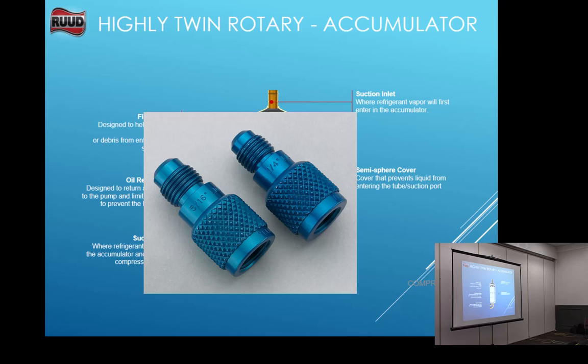Mm-hmm. It does. But once you do it for 2 or 3 weeks, you will get used to it. Because none of the refrigerants we use anymore are supposed to go in the suction line as a liquid. Okay? I'll pass this around. Y'all can look at it. But just keep that in mind. Okay? It's going to save you from killing compressors. Which we've had some of them on startup die. It's probably that. Just keep that in mind.